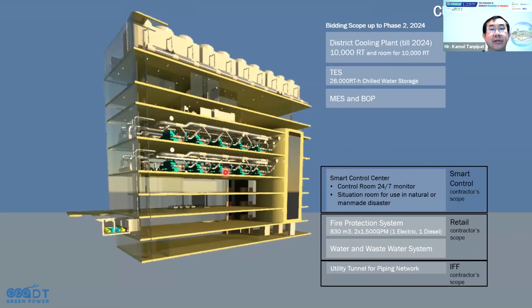You will see here that this is a 6-story building. The chillers, which are the main machines for the district cooling plant, have been installed in 2 stories, one is 10,000 each. In the district cooling system here, we also have the thermal energy storage tank, which is a chilled water tank. The capacity of the tank is 26,000 refrigeration ton hours. The purpose of the tank is, first of all, to reduce the peak demand, and second, quite important, to manage the operations of the chillers to get the maximum efficiency of the system itself.